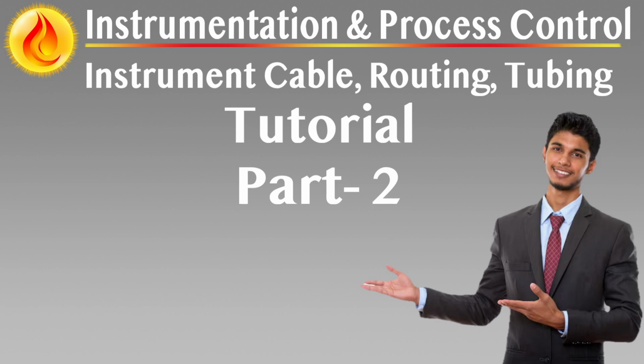Preferred communication mediums for lightning-prone installations. For long-distance or interbuilding communication lines, particularly where routing through lightning-exposed zones is unavoidable, fiber optic cables are preferred. Optical fibers offer complete immunity to electromagnetic induction and lightning transients, and their dielectric properties eliminate the risk of introducing dangerous voltages into protected systems.